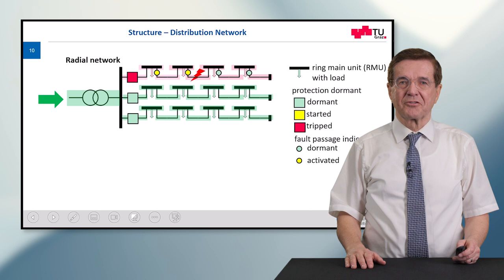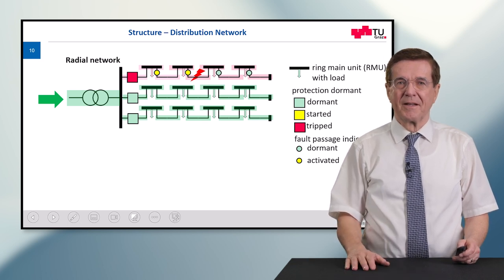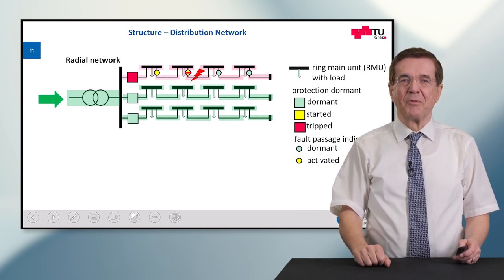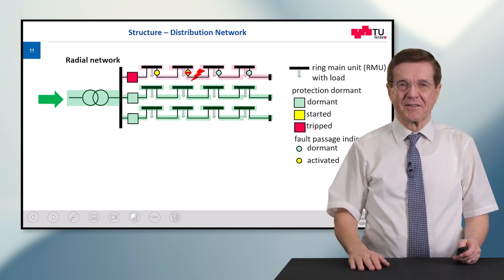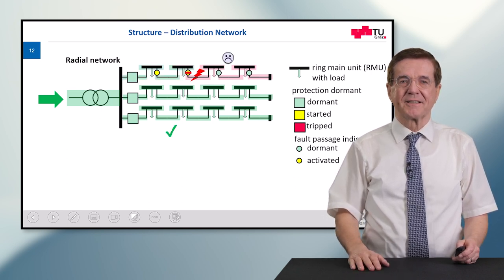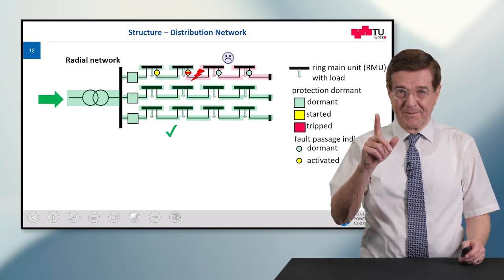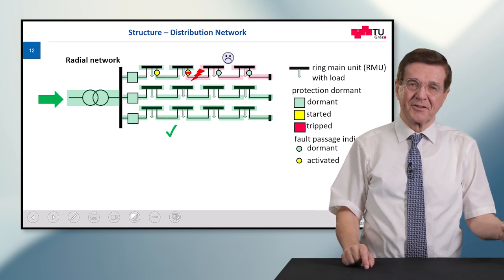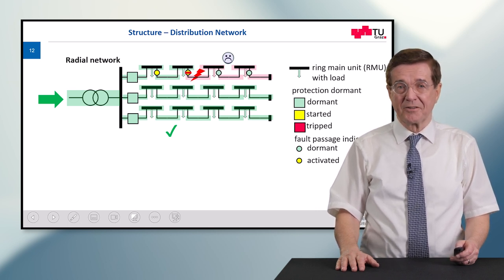After a short time, protection trips this feeder and the electricity supply is lost to everybody. Operations staff then open one circuit breaker — the last one upstream of the fault — and re-energize the feeder at the substation. This means everybody is back on power except those at the end of the feeder: 50% of the line is on power, 50% is out of power until the fault is repaired, which may take quite a time.